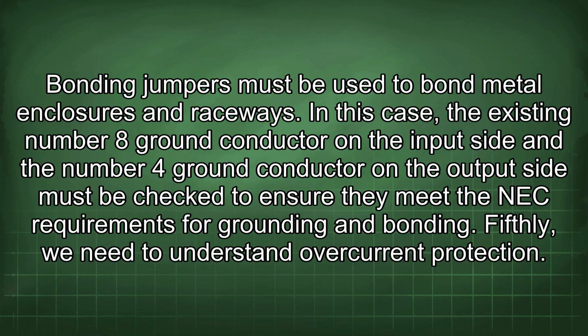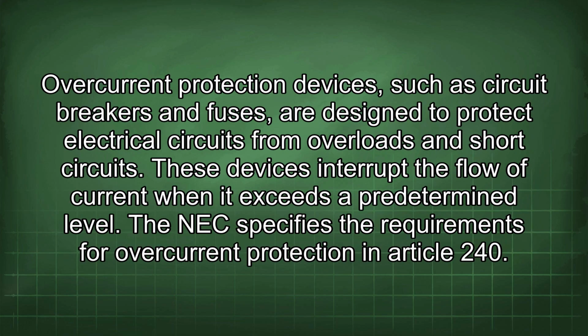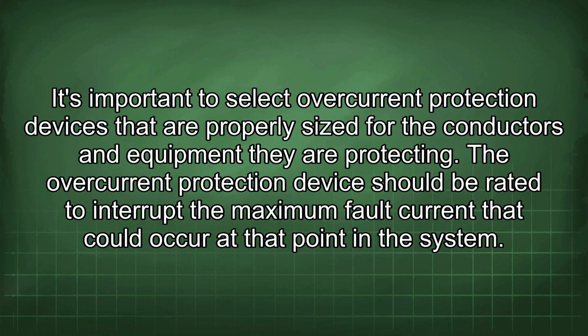Fifthly, we need to understand overcurrent protection. Overcurrent protection devices, such as circuit breakers and fuses, are designed to protect electrical circuits from overloads and short circuits. These devices interrupt the flow of current when it exceeds a predetermined level. The NEC specifies the requirements for overcurrent protection in Article 240. It's important to select overcurrent protection devices that are properly sized for the conductors and equipment they are protecting.